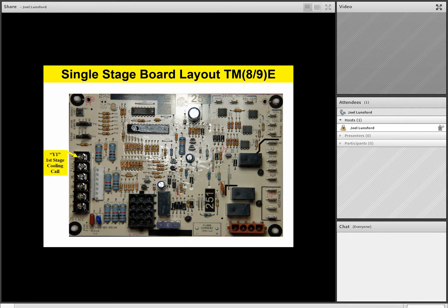So starting in the left hand corner, we see that Y1 is our first stage cooling call. When our thermostat calls for first stage cooling, this board actually has the capability of 2-stage cooling, even though it's a single stage heating board. So Y1 is our first stage cooling call from the thermostat. Y2 is our second stage cooling call from the thermostat.